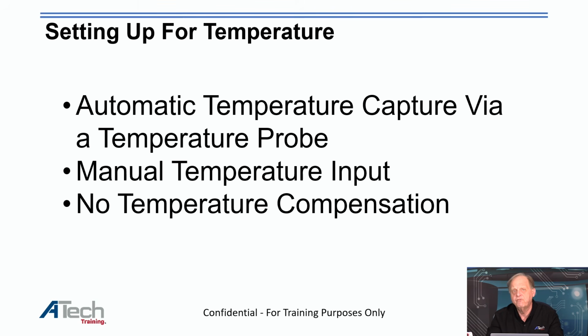So if your settings are at 72 or 74 degrees and it has a conversion factor, let's say the manual said you should be at 68 degrees and you're supposed to have this reading of ohms in the system. What you would do is hit the conversion factor, and that would compensate for the slight changes in the temperature and give you a reading at the temperature you would normally be testing. That makes it a little bit easier. So it's doing a temperature correction factor for you automatically.